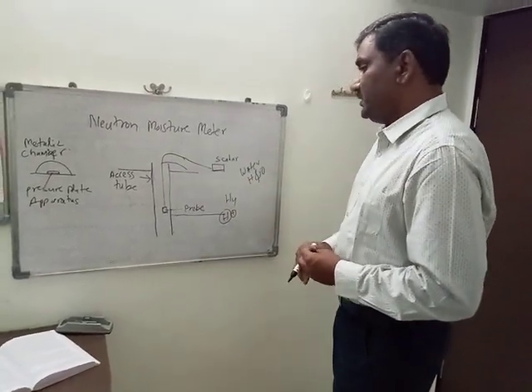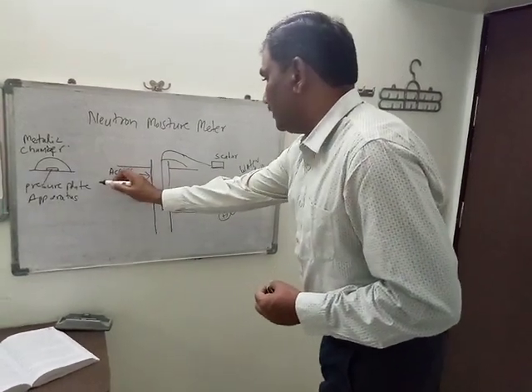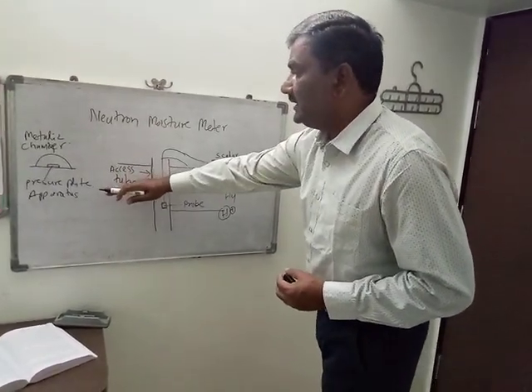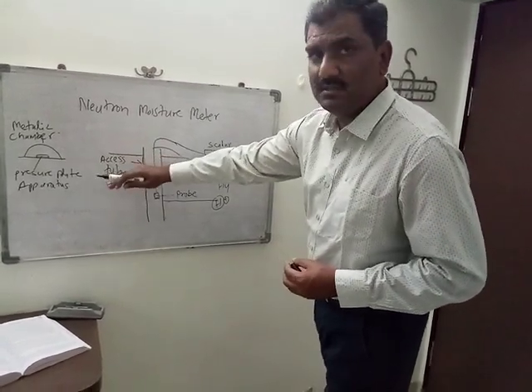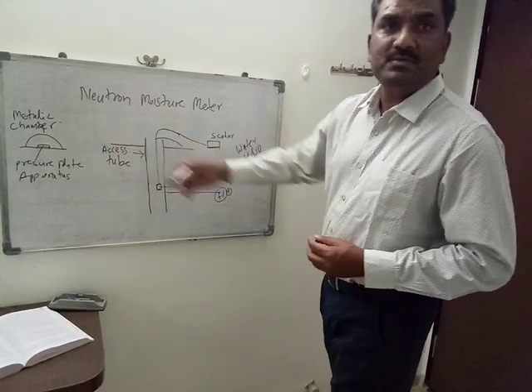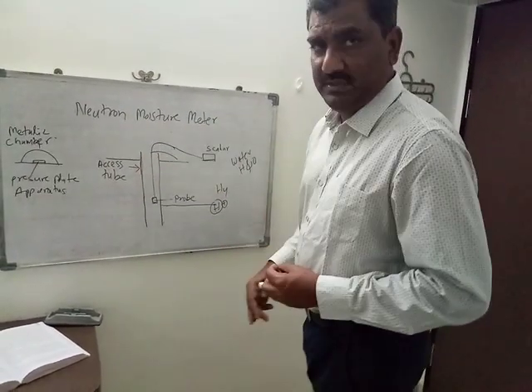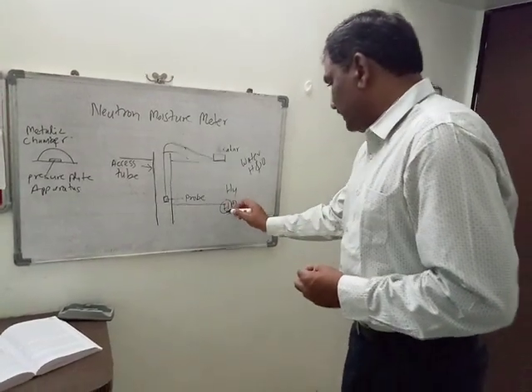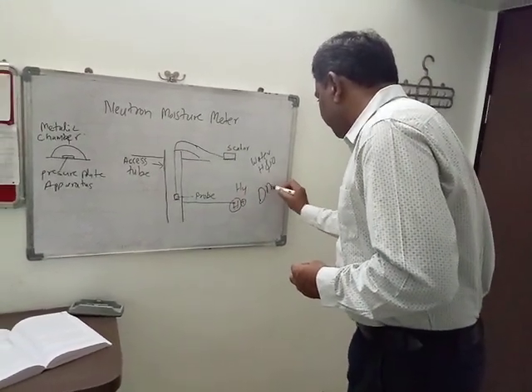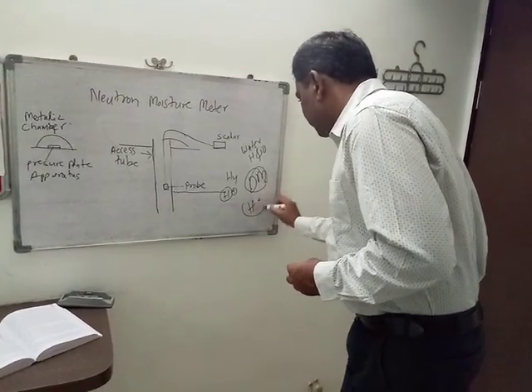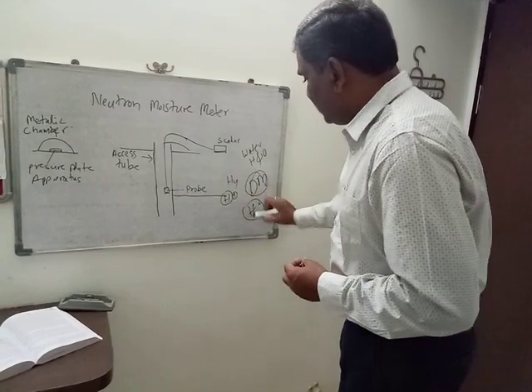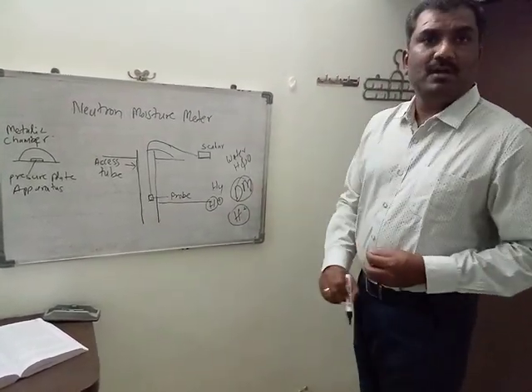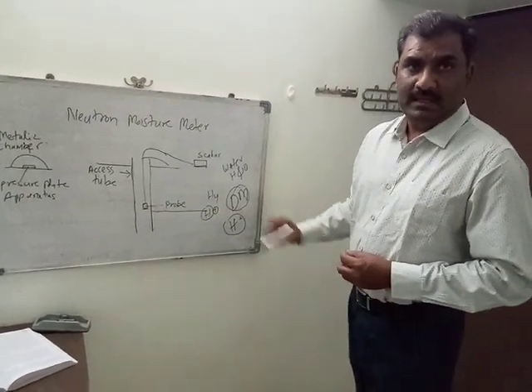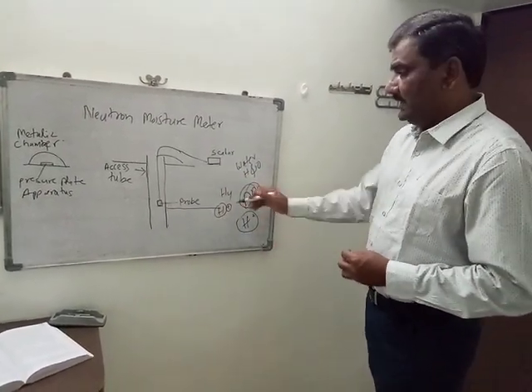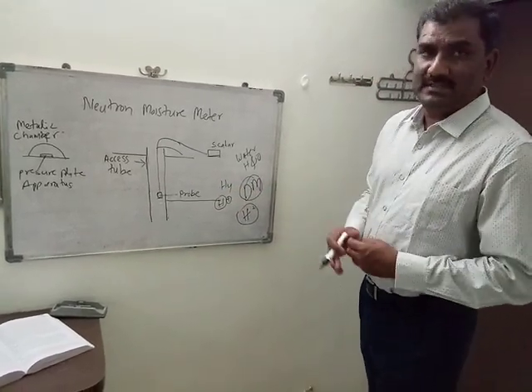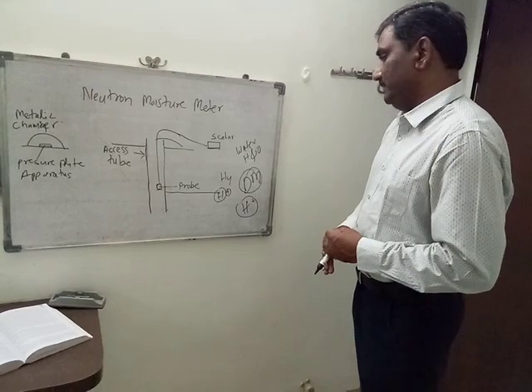Only one issue is there: when we go for soil moisture measurement at shallow layers, it is difficult, or we can say hazardous, because the radiation can cause some damage to the persons taking the observations. This is one. Second, organic matter also contains hydrogen atoms. So this source will detect these H ions present in the organic matter also, and this will mislead the observations. Also there are other ions like chlorine and zinc which it can measure, and that will give false readings. So that is one of the demerits of this instrument.